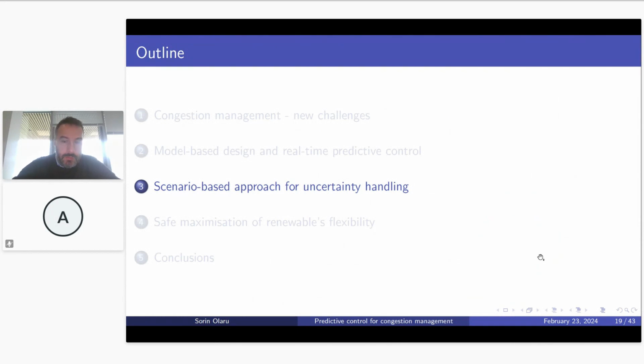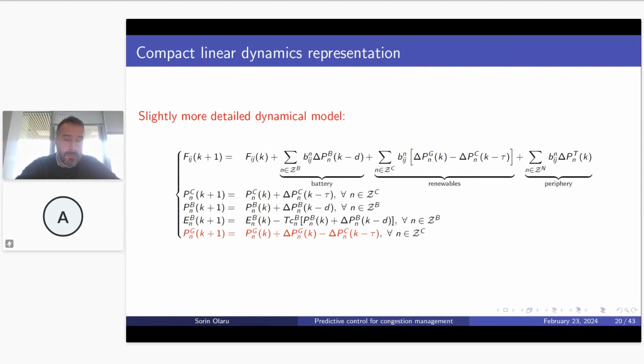Okay, I'll try to speed up. There are variations around this idea. So what we noticed is that as we are taking into account the worst trend with respect to the production, we can be sometimes very conservative and start sending curtailment orders as soon as the battery is full and the trend of production is aggressive. So in order to handle that, we went into a scenario-based MPC instead of taking the worst realization of the disturbances.